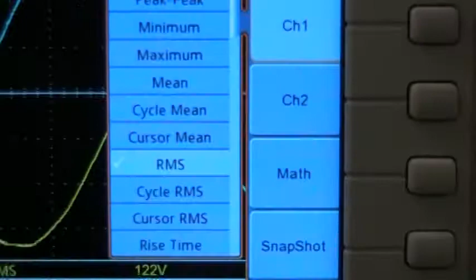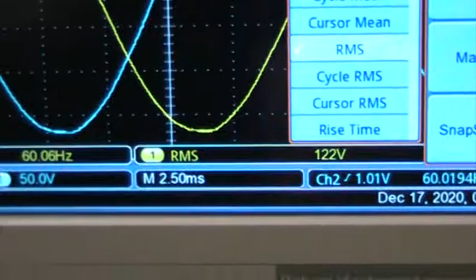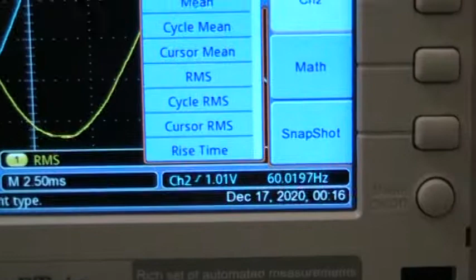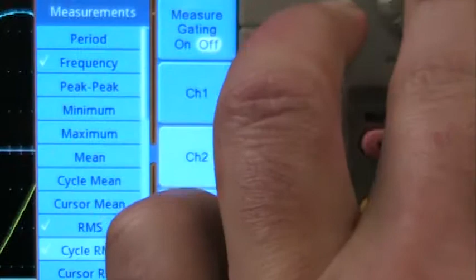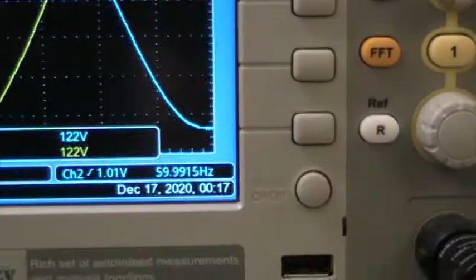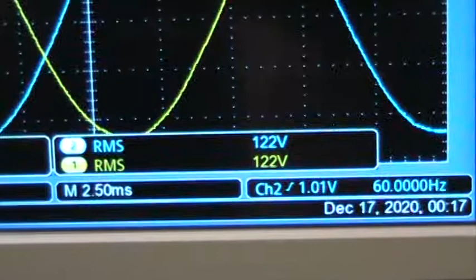So I can already see, for my channel 1, which is what's in blue, this is the RMS value, it's 122. In theory, it's 120, but in practice, it's not exactly that. And the frequency, which does vary a little bit, but it's close to 60. And so I already have that. So I can go now to channel 2 and also select what I want to measure. So with my knob here, I'll highlight frequency, and I'll also highlight the RMS. No, I selected the wrong one. Now I got it. So now I'll just remove the menu. That's all I need. So we can see both of them. See the RMS of the blue line and the yellow line are both measured. That's 122. And you can also see the frequency for both.